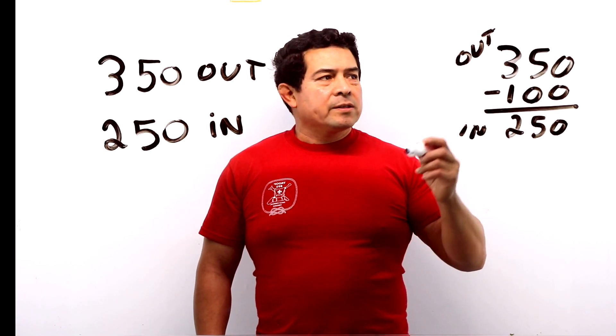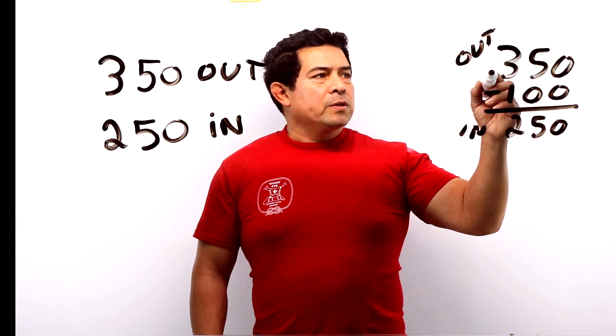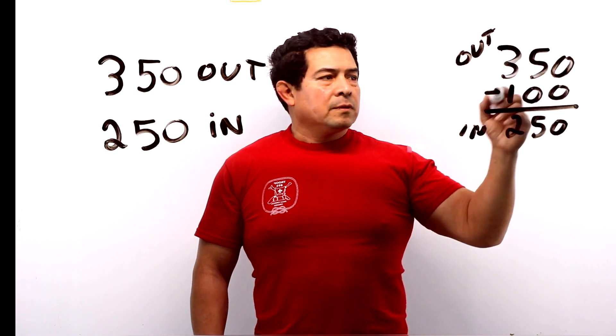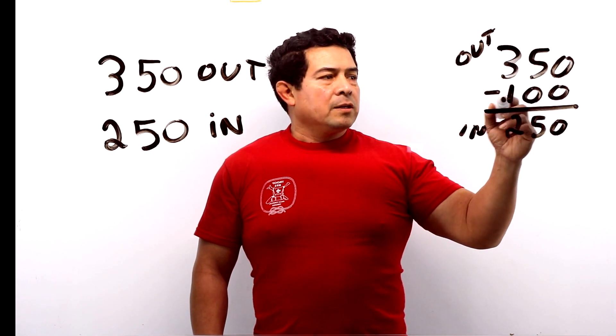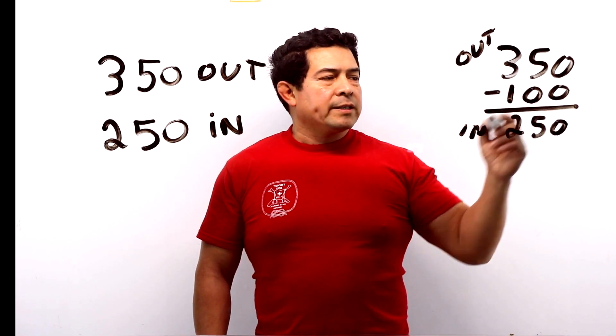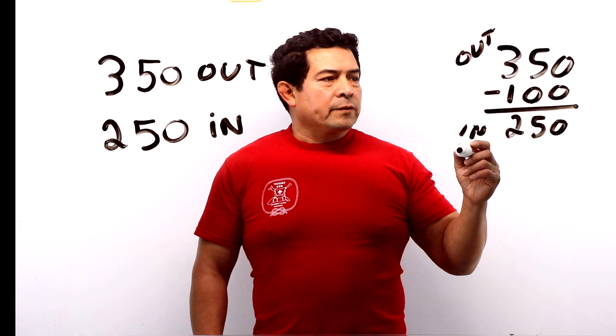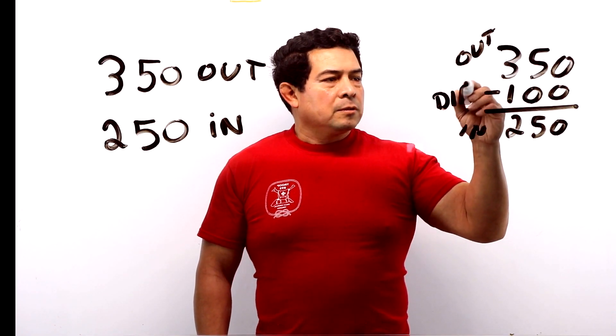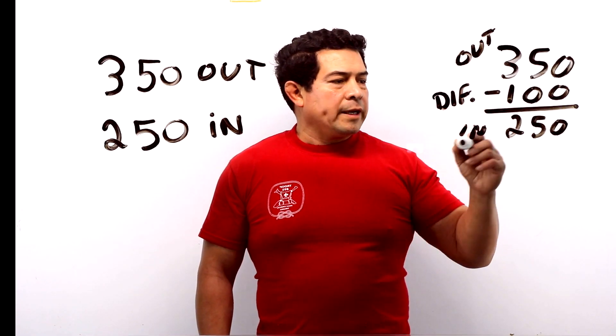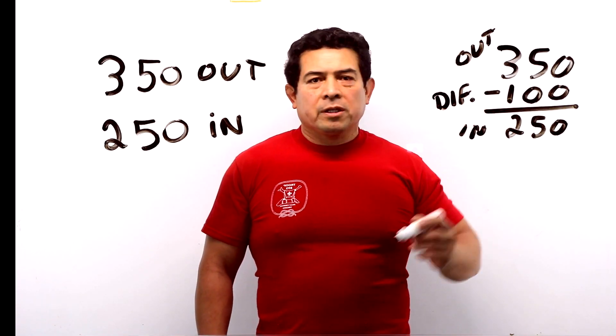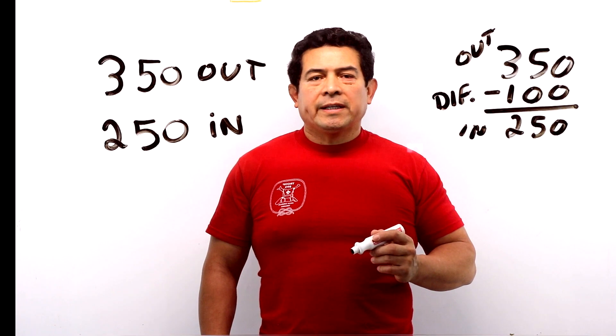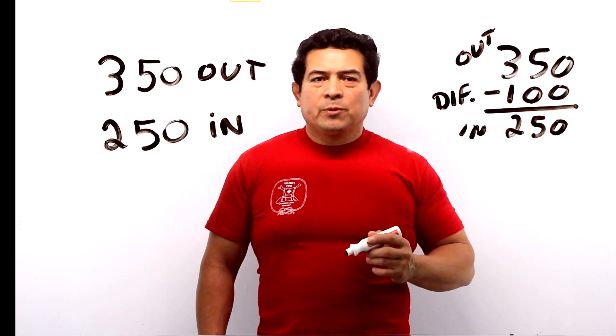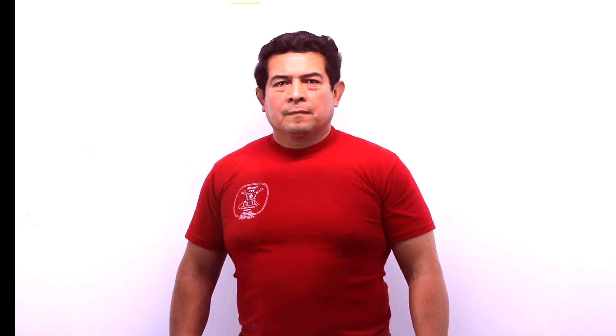By looking at this, all you do is set the cut out, then you set the differential and that will tell you what the cut in is. That's how you would set your high pressure switch.